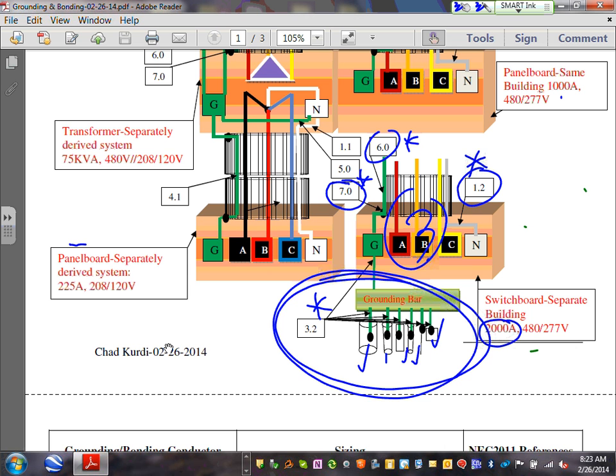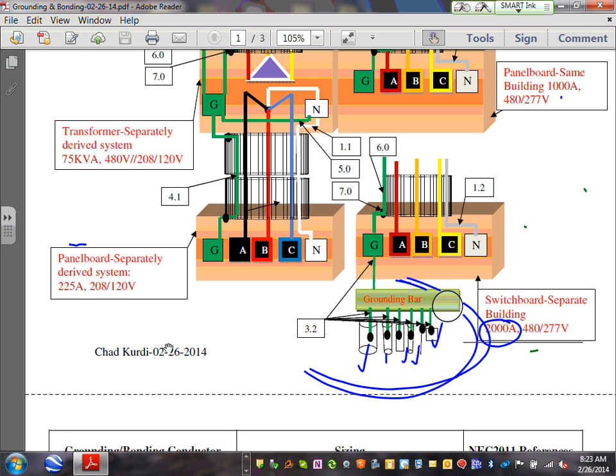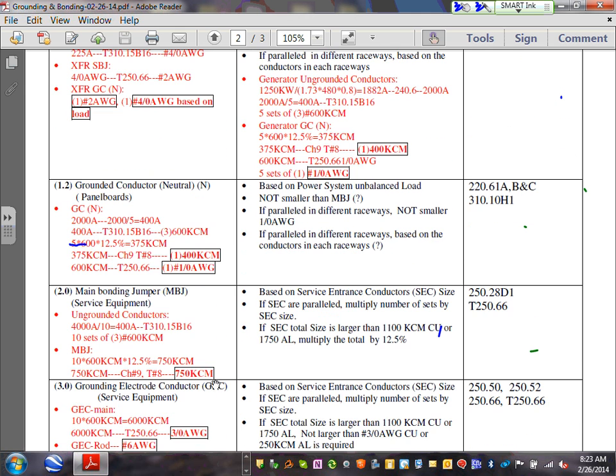The separate building? All right, so the separate building, my friends. Now, let's go to 1.2, and the same thing for the separate building. Okay, so let's go to 1.2. 1.2 is right here, gentlemen. Actually, we were looking at it before. For 1.2, here's the grounded conductor, guys. Exactly, and we came up with 400. Either one conductor of 400 or 5 sets. 5 sets, why not? That's exactly what we were looking at before. So that's how you size the grounded conductor at the second building.